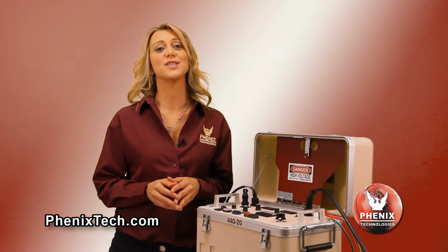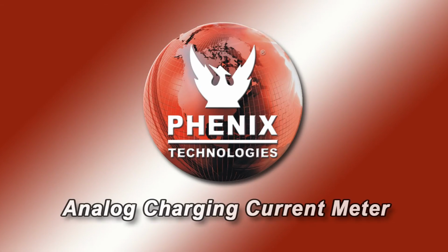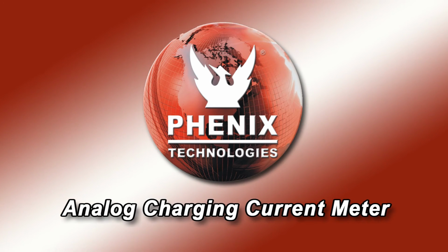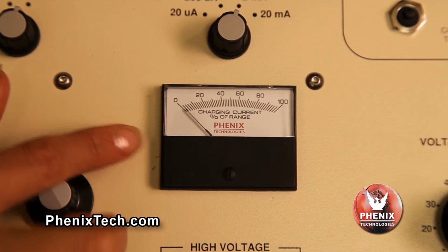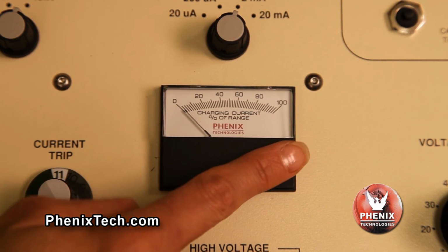Now let's go over some additional design and safety features of these Hipots. The analog charging current meter. This meter indicates % of output charging current for a selected range. An overtrip current may be avoided by the operator monitoring the meter and by adjusting the voltage rate of rise to control the output current.